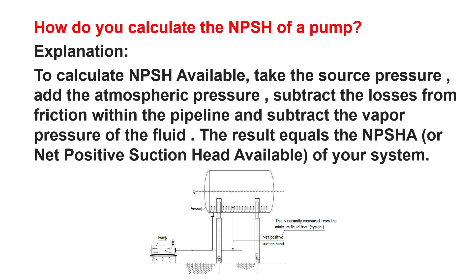How do you calculate the NPSH of a pump? To calculate NPSH available, check the source pressure, add the atmospheric pressure, subtract the losses from friction within the pipeline, and subtract the vapor pressure of the fluid. The result equals the NPSH-A, or Net Positive Suction Head Available, of your system.